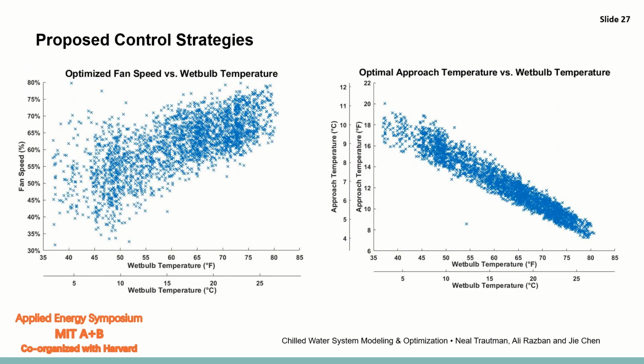And this brings us finally to the proposed control strategy. Since there was no advantage to optimizing the condenser water pump speed, we ended up abandoning that as a potential control strategy, and we looked at how to control the cooling tower fan.